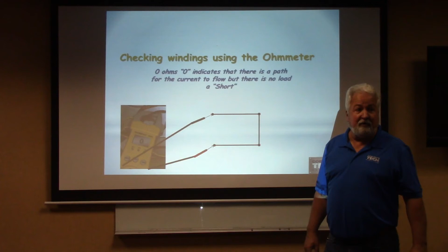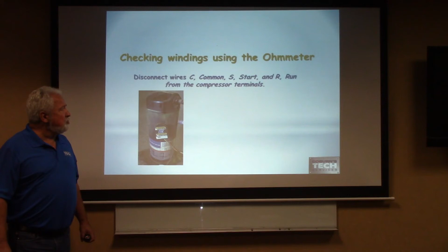Good. So, checking your compressor using your ohm meter, we can identify some stuff. So let's try that. We're going to disconnect the C, the common, the S, start, and the R, run, from the compressor terminals. And this is basically what you're looking at inside there. An ohm reading with a number such as 0.5 ohms or 2.4 ohms states that there's some resistance in that winding. The resistance coil and current flow create the magnetism needed for that motor to turn. Well, common doesn't have a winding. It only has a switch.